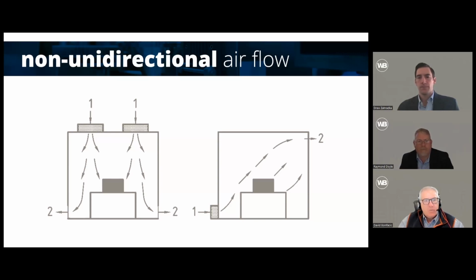Ray, can you give us some examples of where you would apply, in your experience, where this has been applied? No, that's good, Dave. So in microelectronics, clean room, chip manufacturing, subfab spaces, you'll have a true unidirectional flow where they have everything coming from the ceiling, and they'll have a perforated raised floor across the entire floor, and then all the air goes down through. And so you get this unidirectional flow. It's only ideal in a steady state, and I'll talk about that in a minute, but when the space isn't occupied, people aren't moving around.